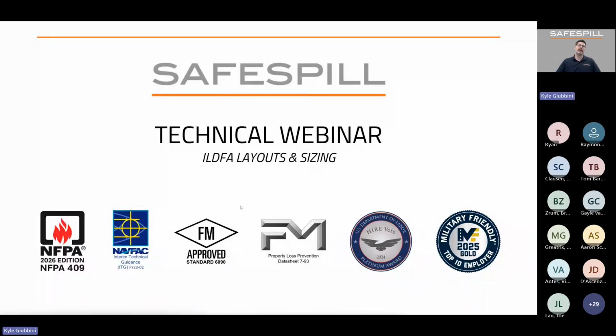And then finally, on the FM side, the Safespill floor is an FM approved product. It was evaluated under a new product approval standard, which is standard 6090 for ignitable liquid drainage floor assemblies, or ILDFA. I was involved in the initial testing for our FM approval in 2017, as well as our second approval that was obtained in 2020 with some critical design improvements. And then finally, FM has property loss prevention data sheet 7-93 for aircraft hangars. We will touch on this document today, but this is the 2022 edition where ILDFA was included.